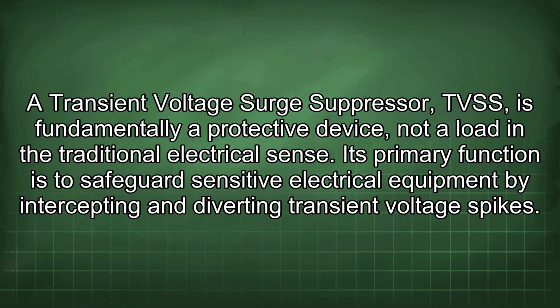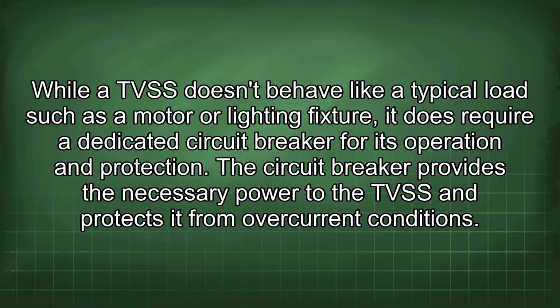A transient voltage surge suppressor, TVSS, is fundamentally a protective device, not a load in the traditional electrical sense. Its primary function is to safeguard sensitive electrical equipment by intercepting and diverting transient voltage spikes. While a TVSS doesn't behave like a typical load such as a motor or lighting fixture, it does require a dedicated circuit breaker for its operation and protection.